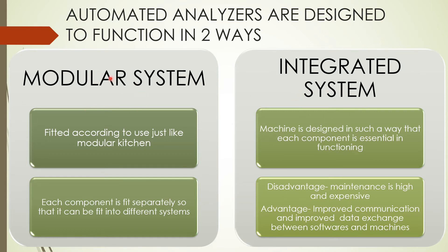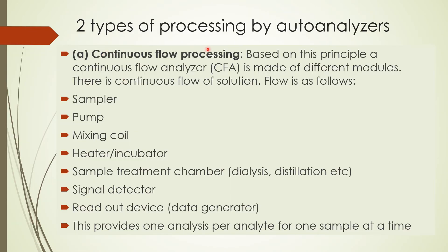Modular systems are the open systems. Based upon processing, there are two types of auto-analyzers. The first is continuous flow processing. Based on this principle, a Continuous Flow Analyzer (CFA) is made up of different modules. The flow is as follows: first the sample, then the pump, the mixing coil, heater and incubator, sample treatment chamber, signal detection, and readout device. This provides one analysis per analyte for one sample at a time — the sample flows through and gives you the result.